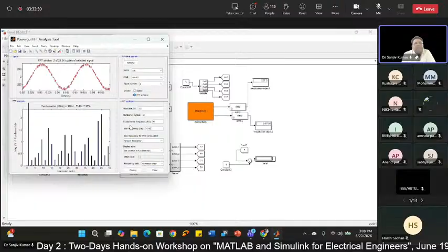If I start from 0.02, number of cycles 2, display, yes, THD is 7.97%. And if I take this as 1000, it will show the real picture. Look at the value of the dominant harmonic, 1.4%. Fundamental is maximum, there is no DC component, and the dominant harmonic is 1.4%.